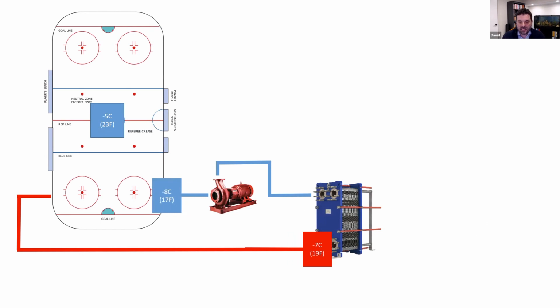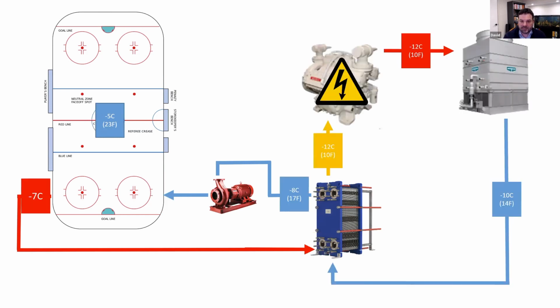When you think about refrigeration systems - like when I first started, one of the things I had to get my head around - is that refrigeration systems aren't really making things cold. They're removing heat and taking it from one place you don't want it to another place. As you can see through the journey, the brine or glycol leaves at 17 degrees Fahrenheit, goes through the floor, picks up a couple of degrees, and moves back into what we call a chiller. From the chiller, there's a secondary loop of ammonia or CO2 circulated throughout the refrigeration system. There's a compressor, it goes to the condenser, and then loops back to the plate and frame heat exchanger, where it takes the heat from the brine or glycol.